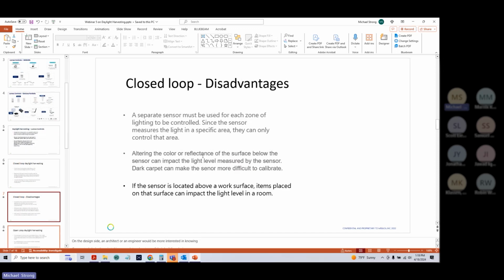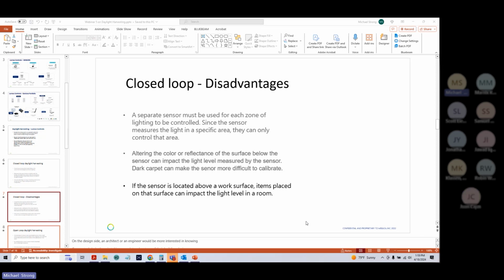Closed loop disadvantages. A separate sensor has to be used, of course. We know that. It has to be in the daylight zone. In California, we are actually required to not just have a daylight zone, but we have a secondary daylight zone as well that we have to read from. So we have two sensors. I would love to just say that we could get away with one and read it further back in the array, but the actual requirements, and if an inspector really cares to enforce, they do require two separate photo cells or two separate light sensors.